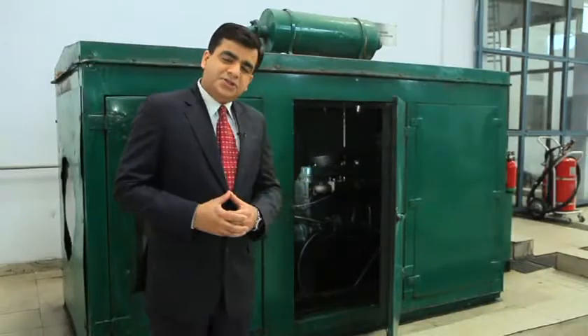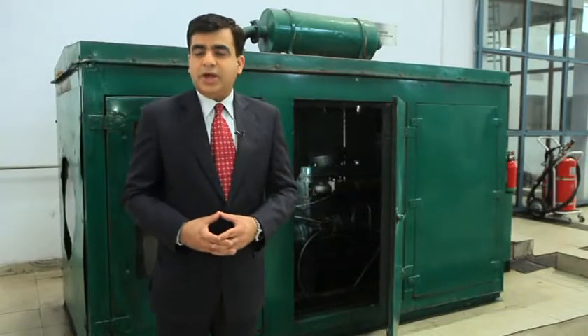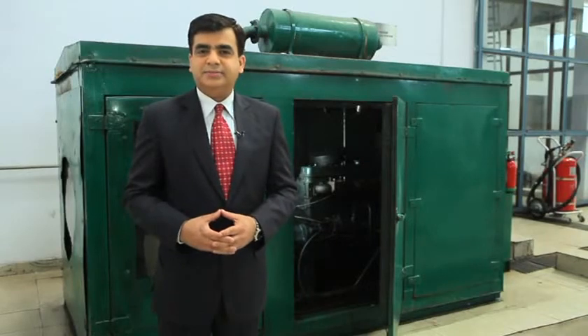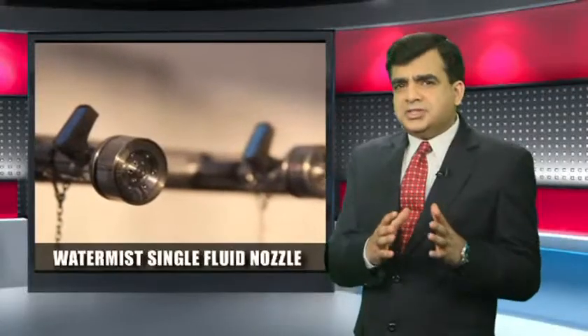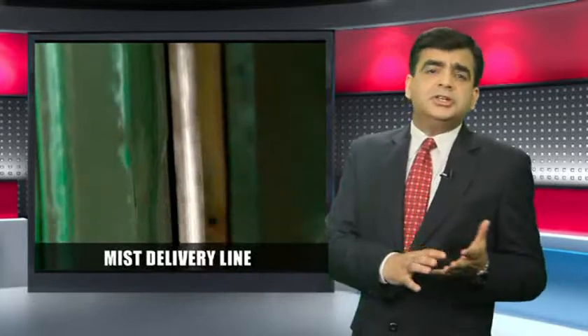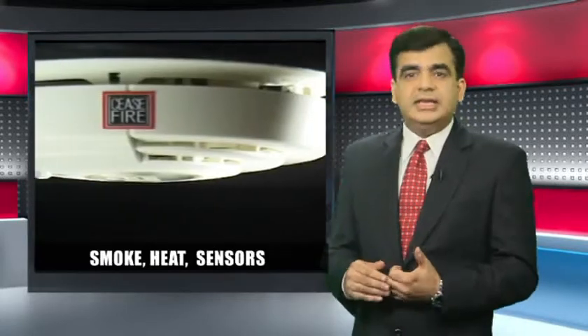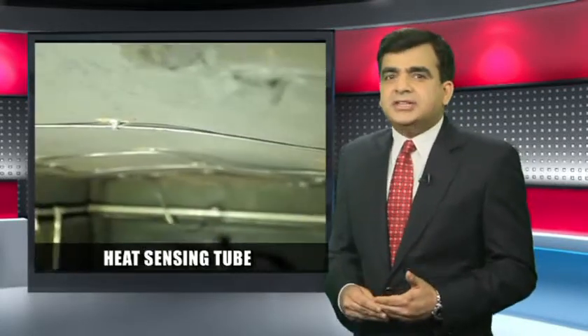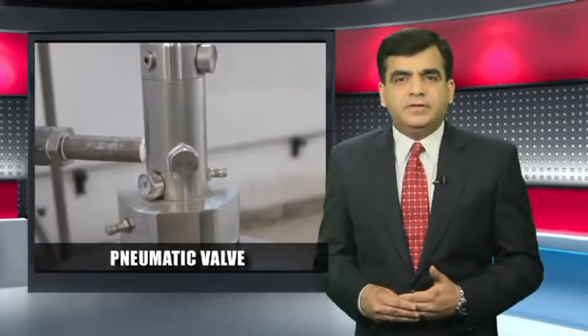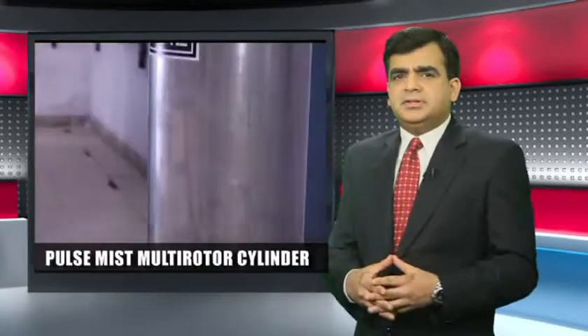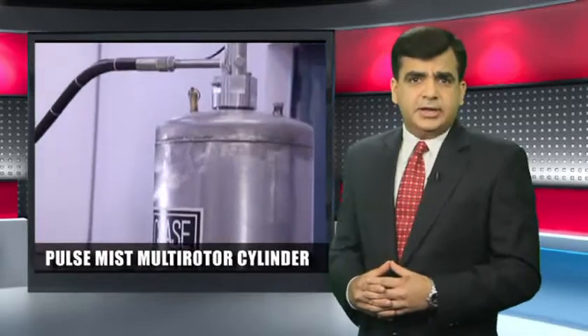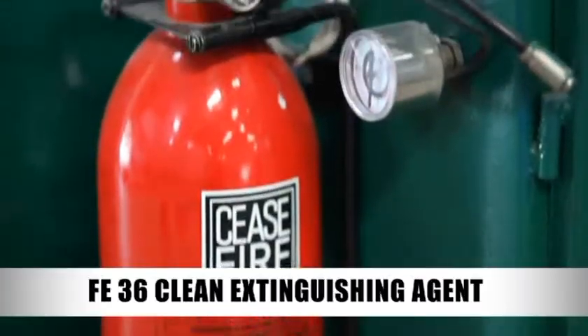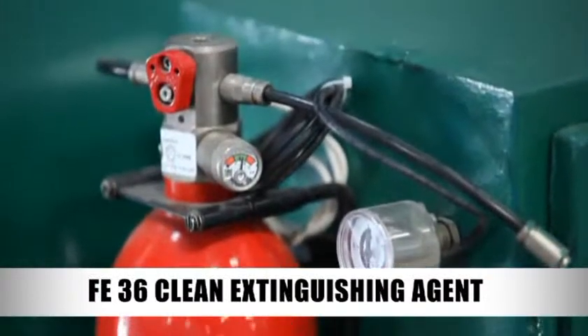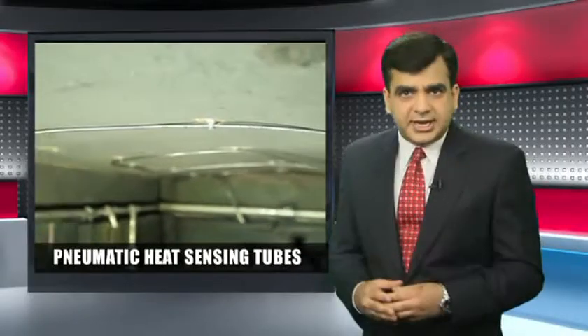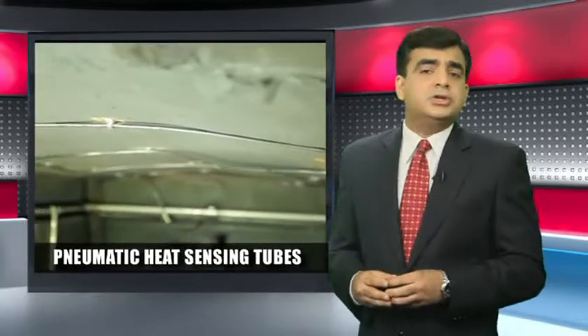This is what the Ceasefire Generator Auto-Quell System setup looks like. It's made up of a water mist single fluid nozzle, mist delivery line, smoke and heat sensors, heat sensing tube, pneumatic valve, control panel, and a pulse mist multirotor cylinder from where the extinguishing agent is delivered. There's also a cylinder with FE36 clean extinguishing agent and pneumatic heat sensing tubes at the generator control panel.